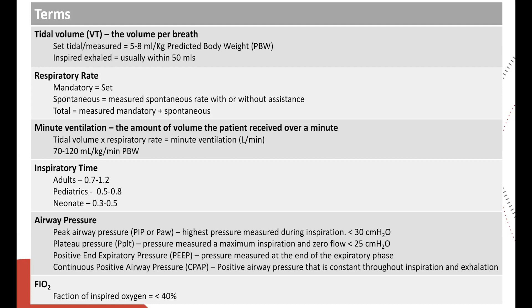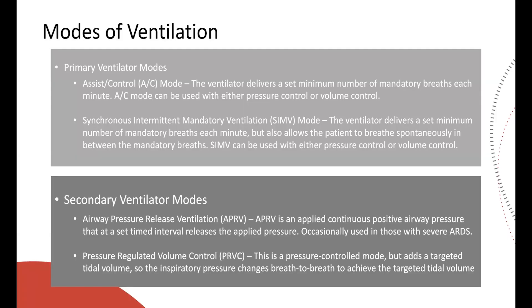When it comes to modes of ventilation, there are several types, and manufacturers even have their own. People often break them down into primary and secondary modes. A primary mode is assist control, where the ventilator delivers a set minimum number of mandatory breaths each minute. When the patient spontaneously breathes, they receive that same set delivered pressure or volume — depending on whether you're in assist control volume control or assist control pressure control. The 'control' term means the ventilator is controlling either the pressure or the volume it delivers.